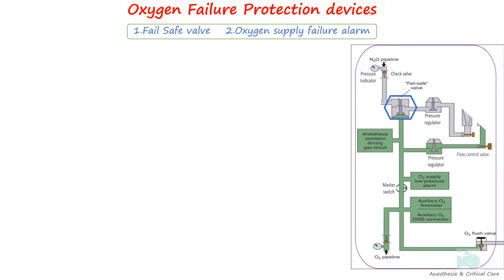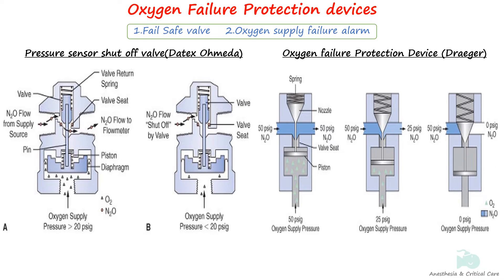One of the serious mishaps with early anesthesia machines was the depletion of oxygen supply, resulting in administration of 100% anesthetic gas leading to hypoxemia. An oxygen failure safety device and oxygen supply failure alarm are installed on anesthesia machines to ensure the patient does not receive a hypoxic gas mixture when oxygen pressure reduces. Machine standard requires that whenever oxygen supply pressure falls, the delivered oxygen concentration does not fall below 19% at the common gas outlet. Different oxygen failure safety device technologies control the amount of nitrous oxide flow depending on oxygen pressure — these are the pressure sensor shutoff valve and the oxygen failure protection device.